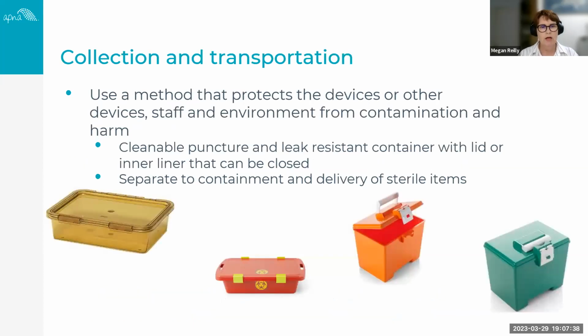So collection and transportation. This process should not cause damage to the RMDs, and it shouldn't again compromise any subsequent cleaning, disinfecting or sterilisation processes. And again, it needs to minimise that risk of drying instruments. So we need to be able to transfer our instruments through to the reprocessing area in a safe way as well. So a cleanable, puncture and leak resistant container with a lid or an inner liner that can be closed. And remembering you can colour code this, you can label it, so it's very clear that there's a difference between the container that contains dirty instruments and the container that contains clean and sterile packaged instruments. Keep it very separate. This is particularly important if you are transporting to another site for reprocessing, or you are sending your RMDs off to an external service provider.